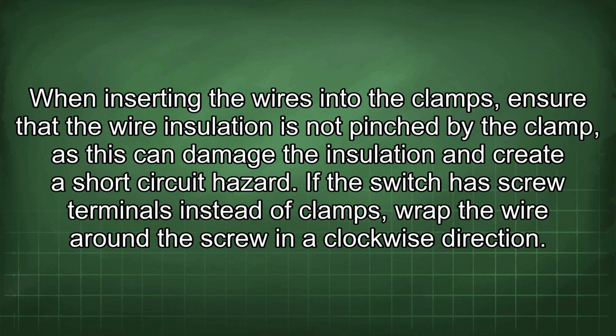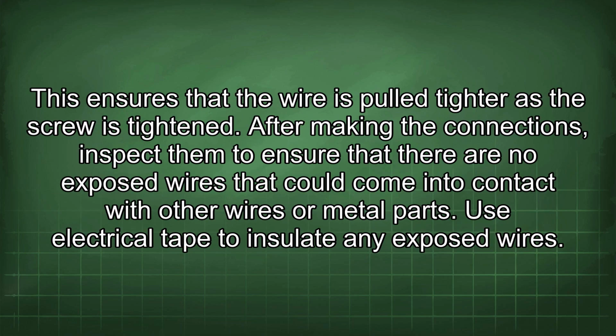If the switch has screw terminals instead of clamps, wrap the wire around the screw in a clockwise direction. This ensures that the wire is pulled tighter as the screw is tightened. After making the connections, inspect them to ensure that there are no exposed wires that could come into contact with other wires or metal parts. Use electrical tape to insulate any exposed wires.